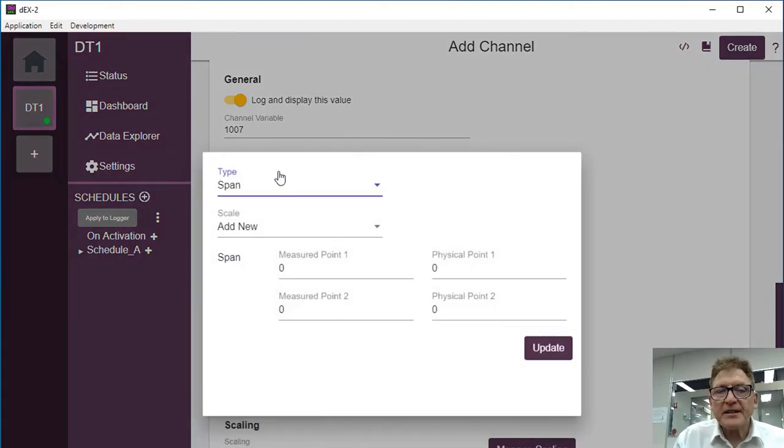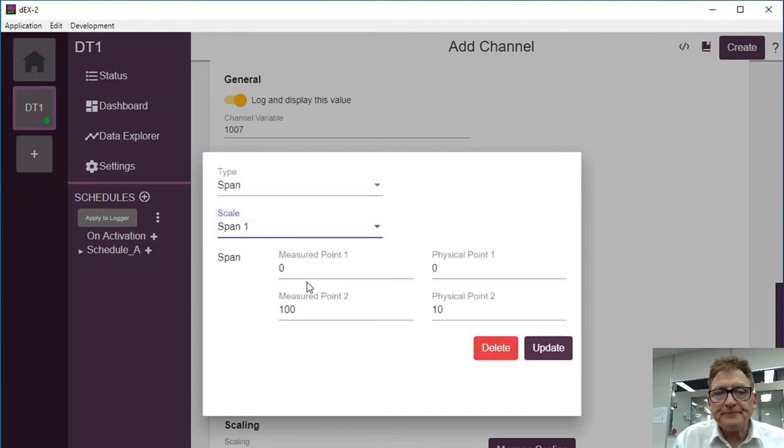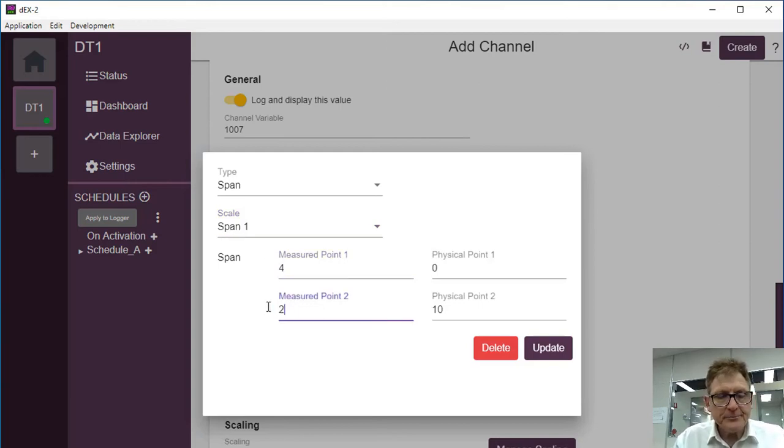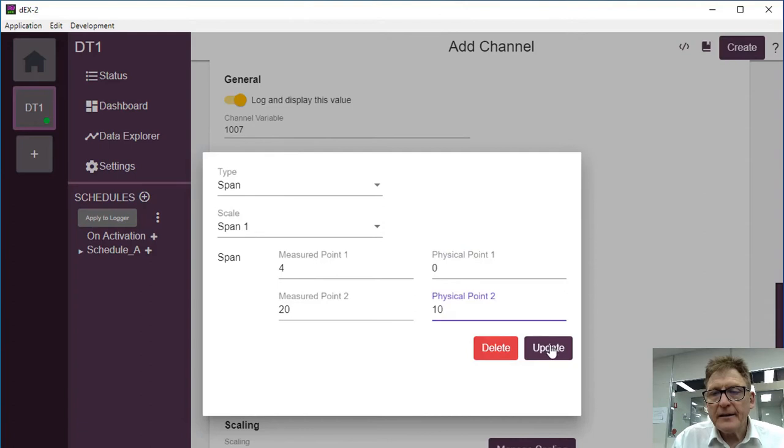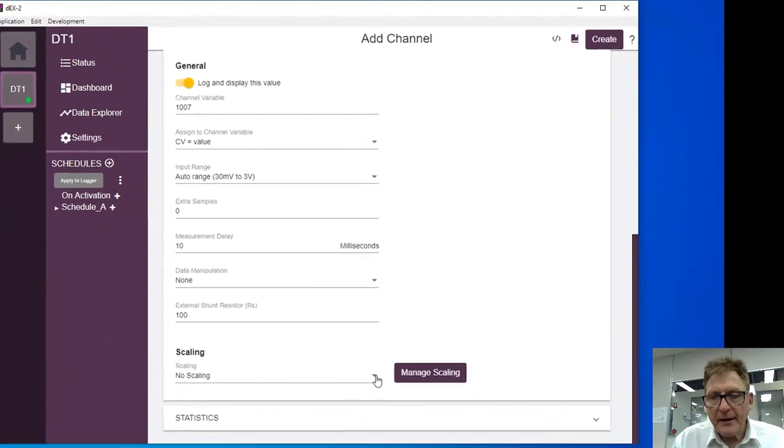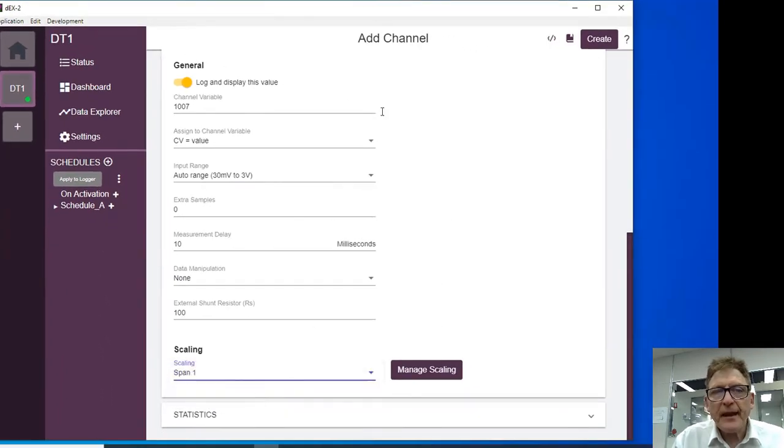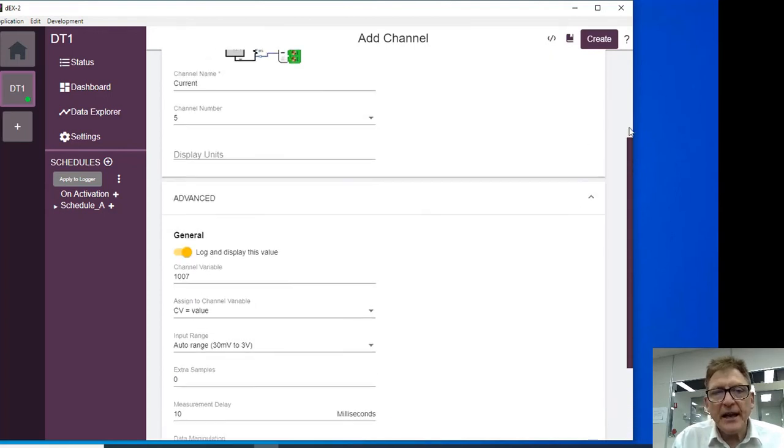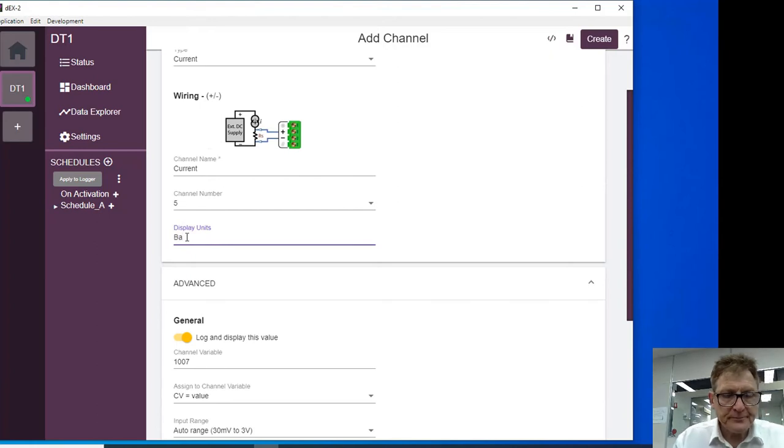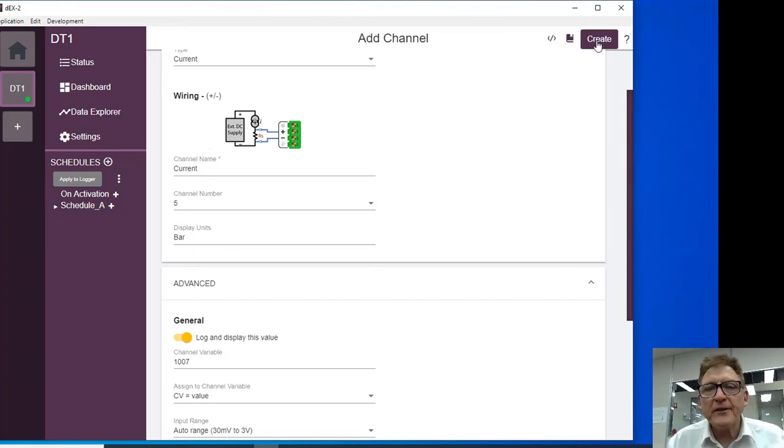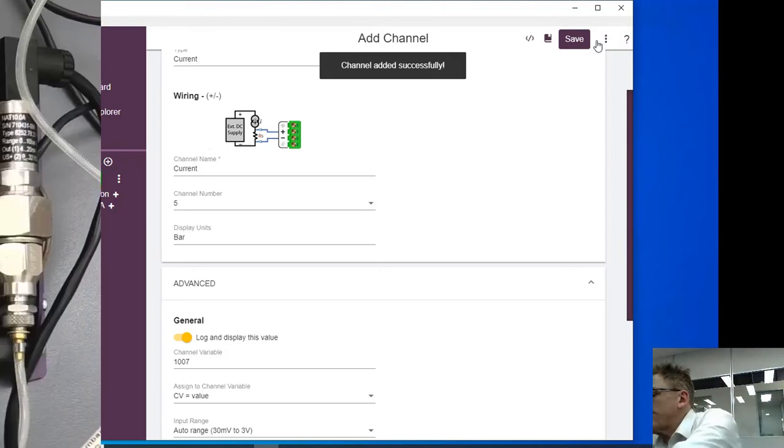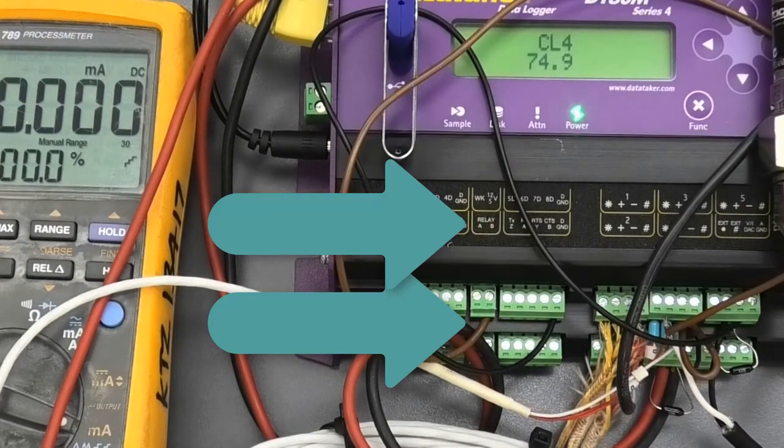We're going to set up a span and I'm going to add new scaling as span 1. The measured will be from 4 to 20, and the physical is going from 0 to 10. Update that. And the units actually displayed - we're going to now select that scaling, which is span 1. And we come back up here and the displayed units are going to be bar. We've configured this, so I'm going to create this channel, but it isn't going to work yet because we haven't turned on this 12 volt supply.